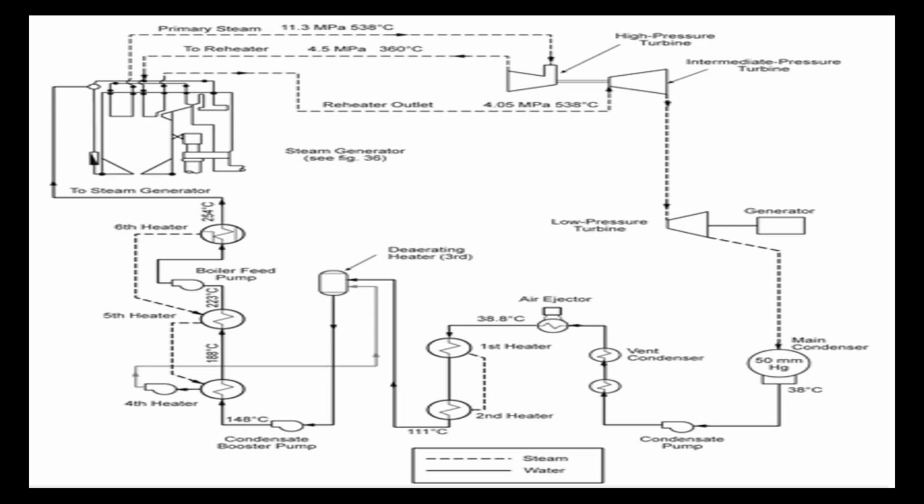Now, in terms of where our feed water is going to go around this loop, what we're basically looking at is the Rankine cycle for our steam boiler and the turbine. So where we'll pick up our water here is at the deaerator. So from the deaerator, which is an open low pressure feed water heater, our water is going to be deaerated where oxygen and carbon dioxide is going to be removed.